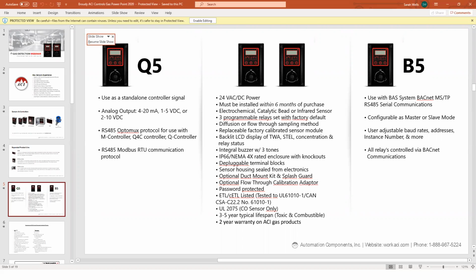Some of the unique features on our Q5s and B5s too, on the CO only, is that our sensors are UL 2075 listed. Some of our competition does not have that. They also come in basically IP66 or NEMA 4X rated enclosures, which is pretty huge. If you're going into an environment that's definitely going to have some wash down, typically fire stations, maybe ambulances or truck facilities where they're going to be washing down, you may want to consider the splash guard on the front just to help protect the sensor.